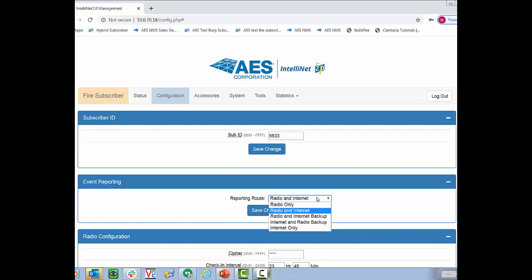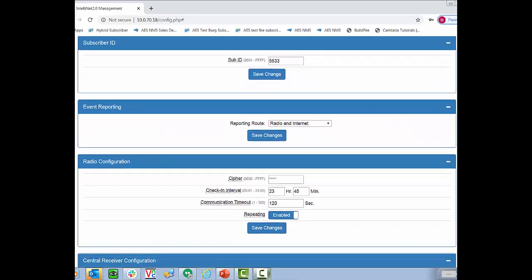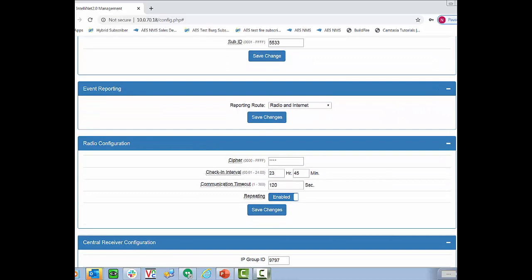The reason for the internet only is if you want to put a subscriber at a customer location but they don't have a radio network built up around them. What you can do is select internet only and then once the radio mesh network is built up around the subscriber you can switch it over to a radio option. Below that we have our cipher code and our check-in interval which we've talked about previously. Here you can also disable repeating if you don't want this radio doing any repeating. Note though that if you disable repeating this is no longer a UL installation and should only be done in very rare circumstances.